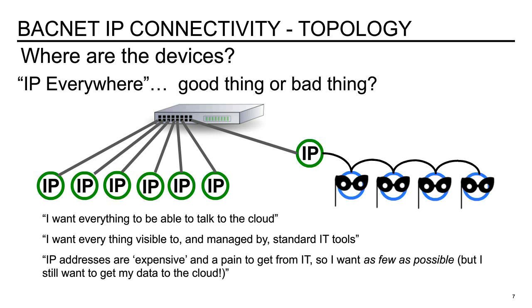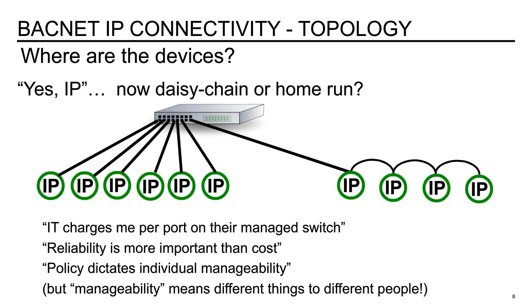We use BACnet IP, and now comes a conversation: do I want daisy chain or home run? Home runs are direct connections between the IP devices and the switch. And the daisy chain is a connection from the switch to an IP device, and then it goes to another IP device, if you look at the slide there on the right. But some of the issues with having IP connections on every device: IT charges you per port on their managed switch. Then you have to weigh reliability versus the cost, and then what policy dictates individual manageability.